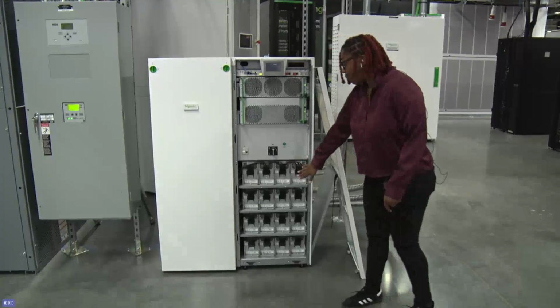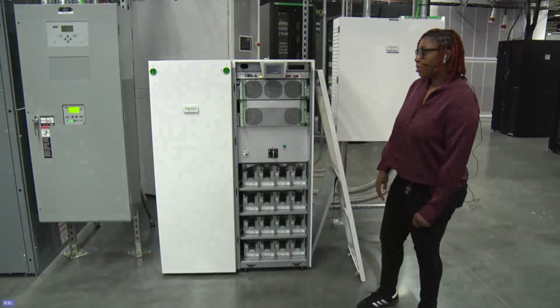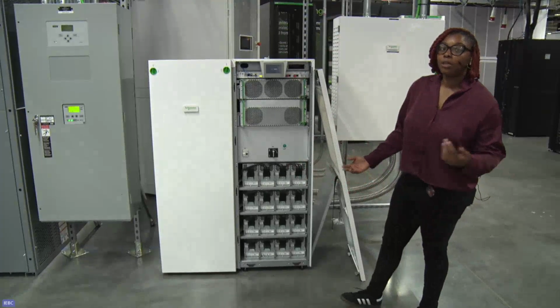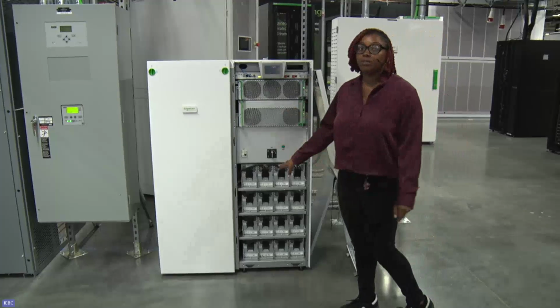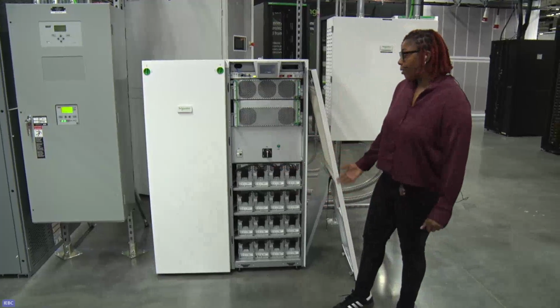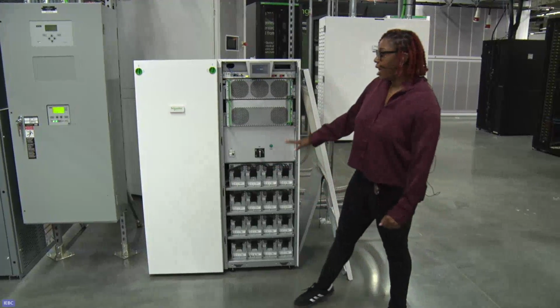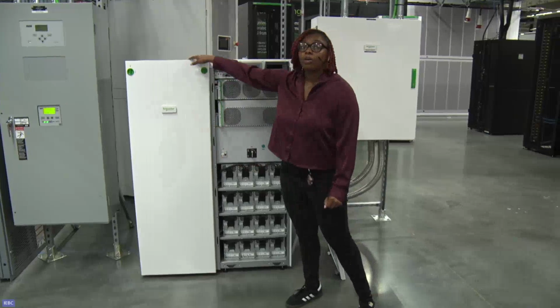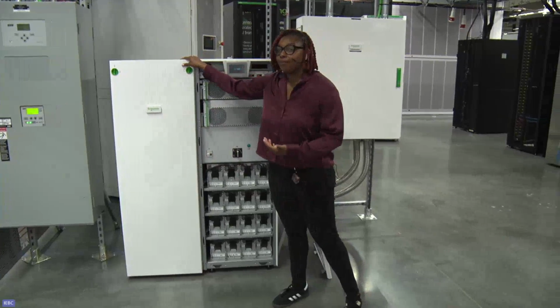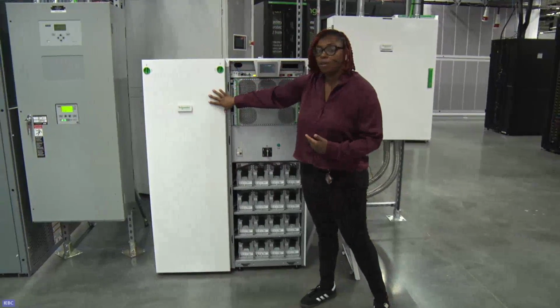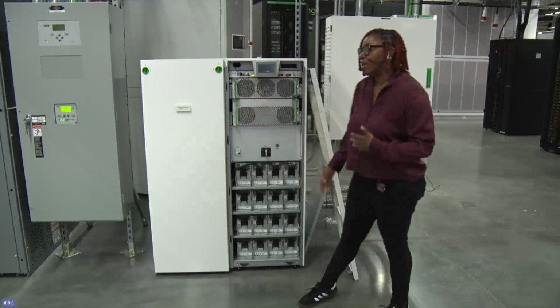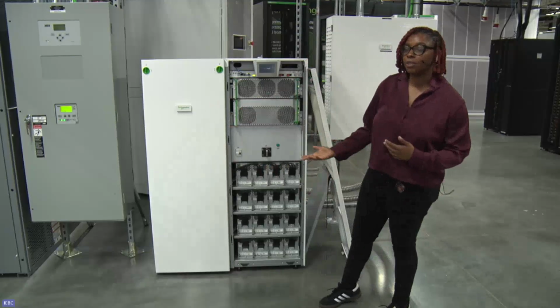There are 4 strings of batteries in here. You do not have the option for lithium ion batteries with this solution, just because of the firmware that comes with this and having the batteries in it. But you can always add additional battery cabinets. So this is an additional VRLA battery cabinet, and you can add as many as you want when it comes to runtime.